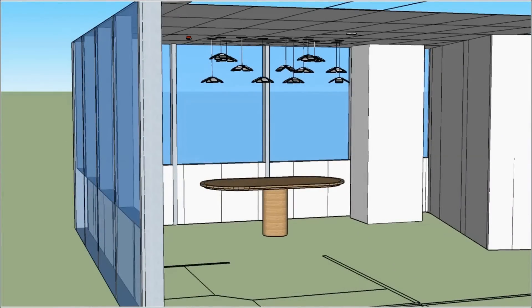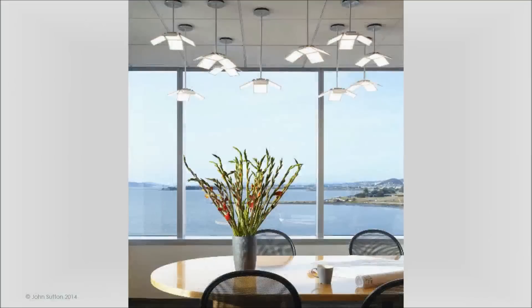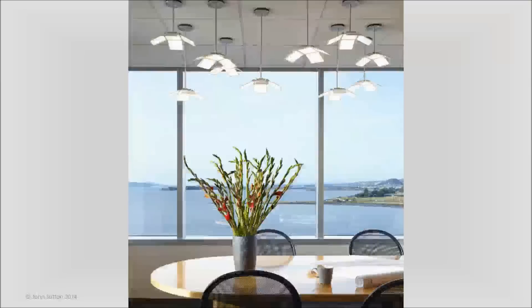This design incorporates random patterns and orientations at varying overall suspension heights, ranging from 12 inches to 24 inches from the ceiling. The results are nothing less than spectacular. Appropriate illumination of 30-plus foot candles at the tabletop provides comfortable task lighting, while complementing the natural, incomparable beauty of the scene right outside the window. The lighting does not block or compete with the view.